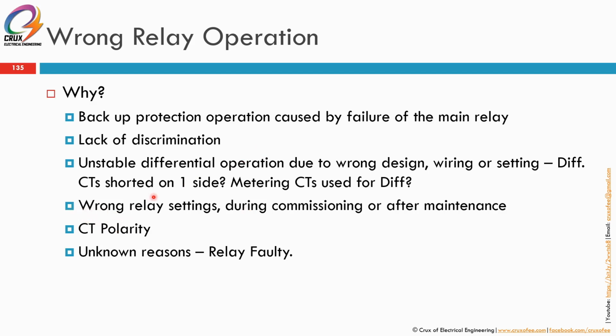number 4 can be due to wrong relay setting during commissioning or after maintenance. This one again, like I said, normally if you want to simulate a high fault by secondary injection, it is not permissible, or maybe your equipment does not allow it to go that high. So what you can do is reduce the setting of the protection and inject using your secondary injection equipment. Of course the test is successful, but once you forget to reset the relay setting to its normal setting, that poses a risk, where it can trip on wrong relay setting.